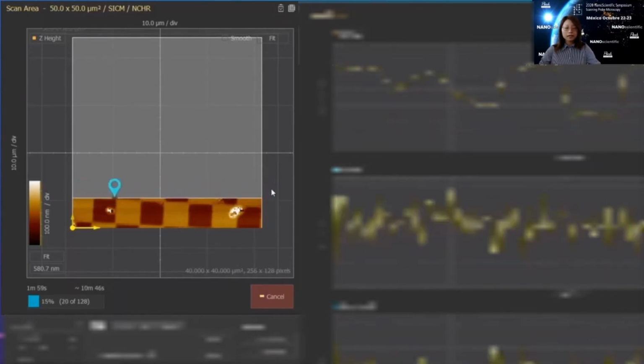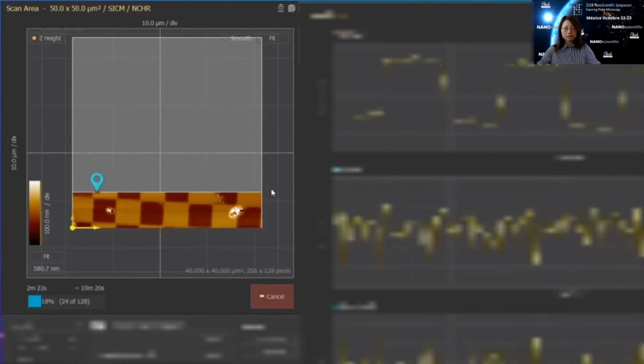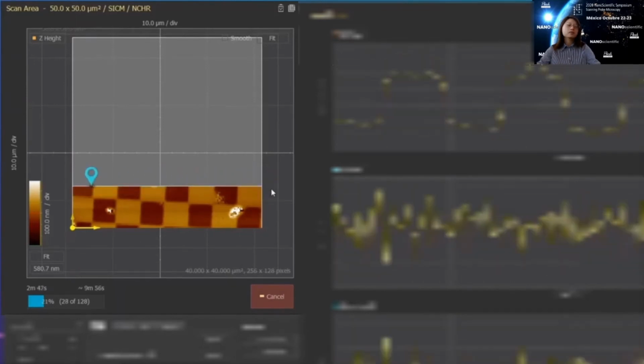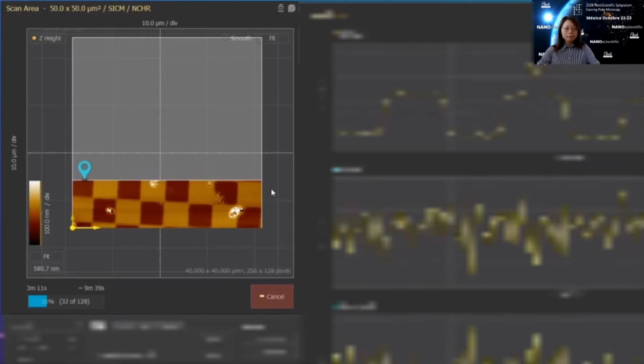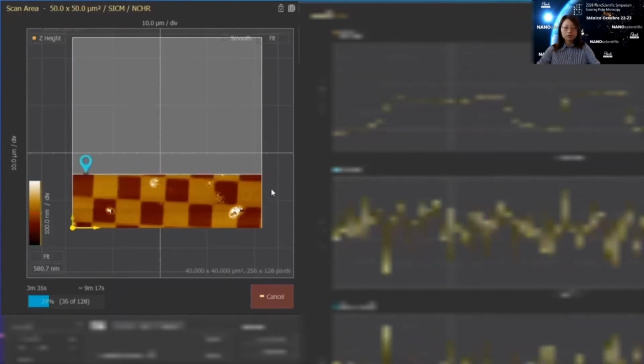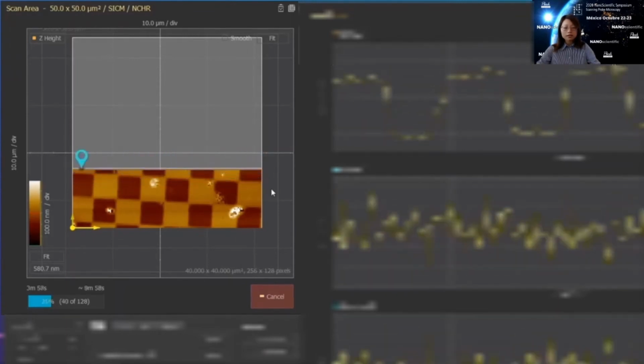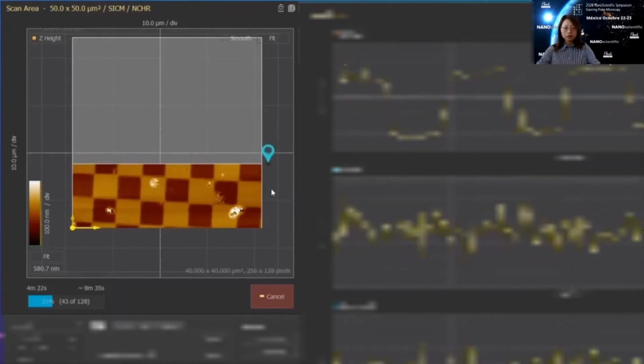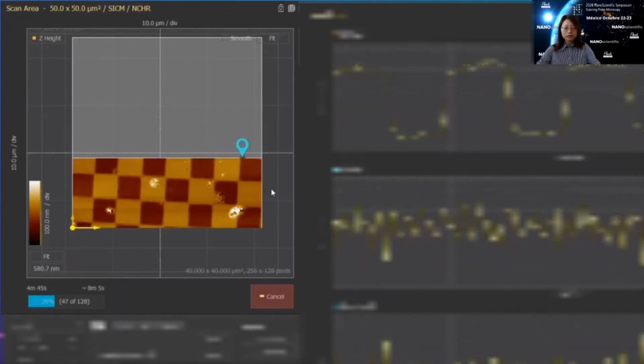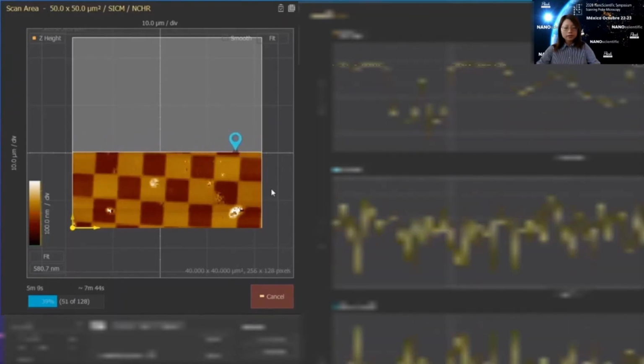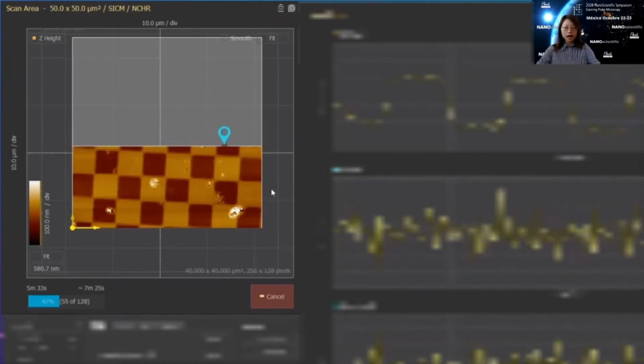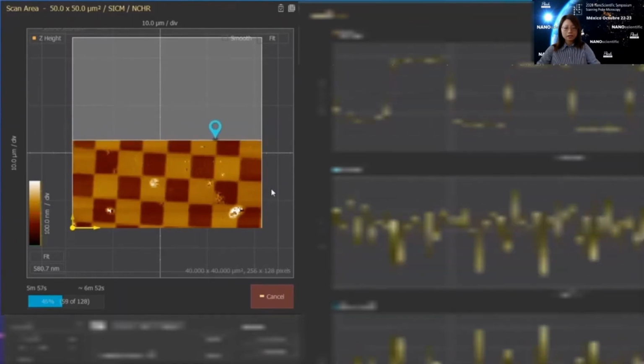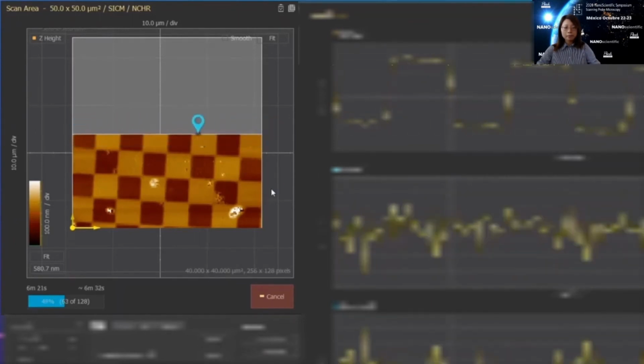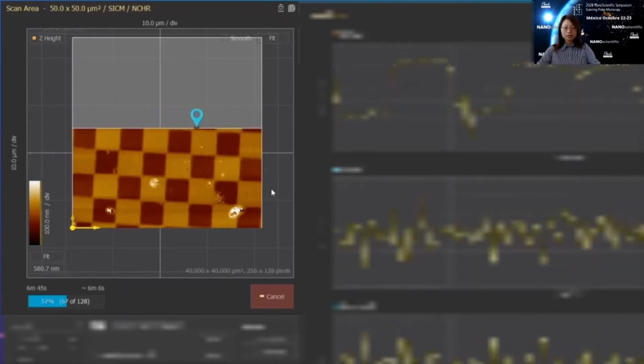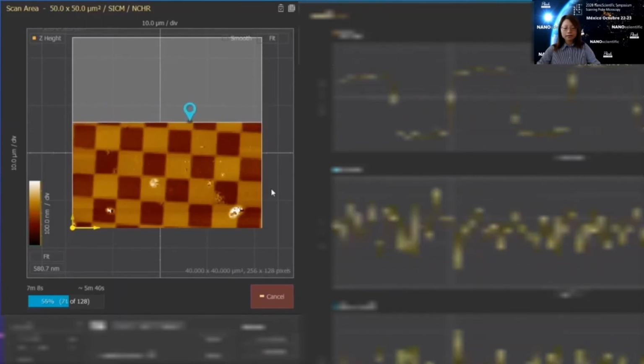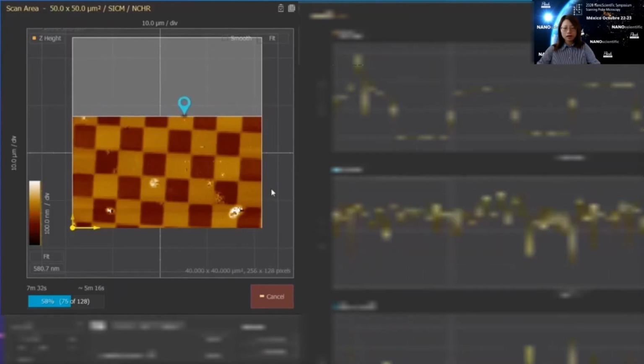ARS mode automatically counters the current drift effect, which can happen during measurements. In this mode, the SICM pipette approaches the sample surface several times at each image pixel. The current difference threshold between the real-time current and set point is about 2% by default. When the measured current falls within the threshold, the height is recorded. The SICM image continues pixel by pixel, thereby removing the dependence on a constant ionic current flow. This creates a stable image setup over time.